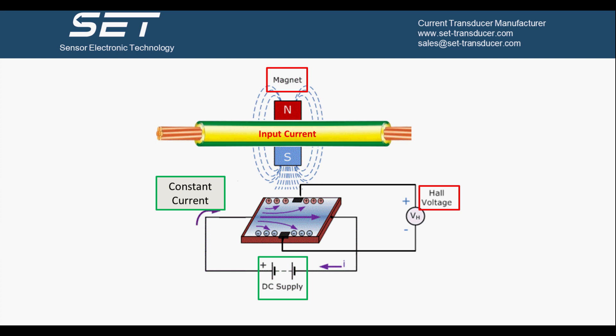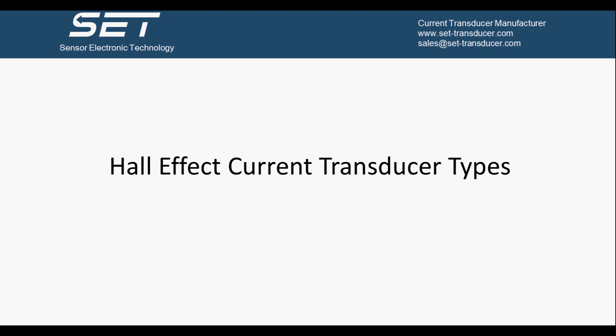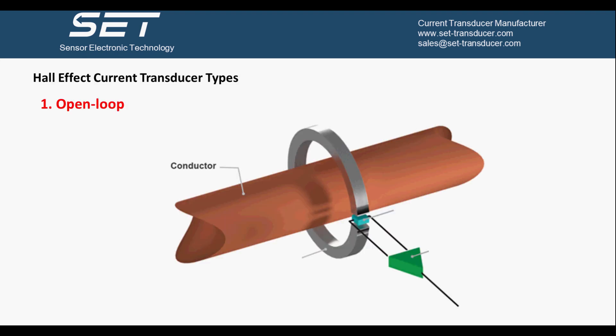Now let's see Hall Effect Current Transducer types. By using the Hall Effect principle to build a current transducer, there are two types of current transducers. The first type is the open loop Hall Effect current transducer. When primary current goes through the conductor, it will generate a magnetic field around the conductor. If we put the conductor through the center of a magnetic core to concentrate the field, and place a Hall element in the gap of the core, we will get the Hall Voltage. The Hall Voltage then passes through an amplifier to become an easy-to-read value.